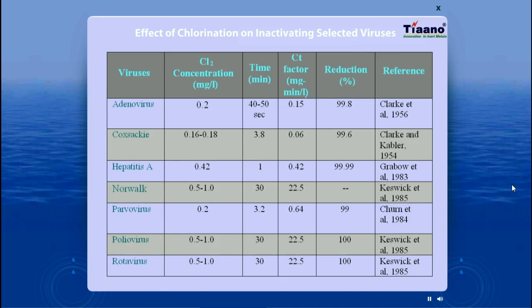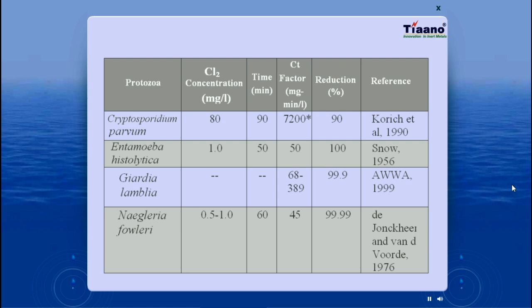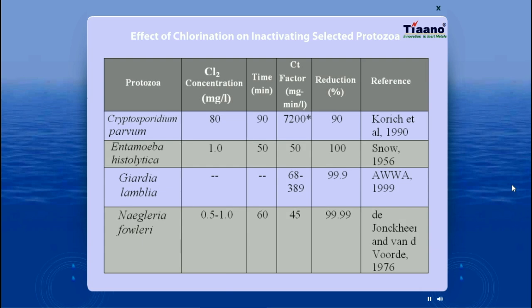This is data regarding the effect of chlorine on inactivating viruses. For example, for Hepatitis virus, which causes jaundice, 0.4 mg of chlorine per liter of water — or 0.4 ppm — in just 1 minute can kill 99.99% of the virus. Protozoa are stronger, and therefore require more chlorine and more time to kill.